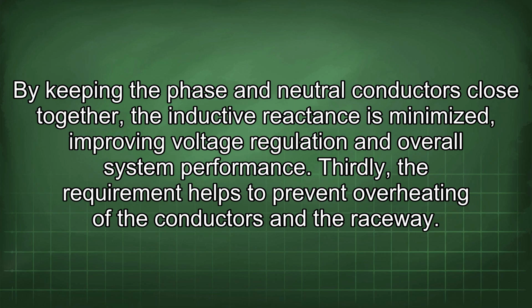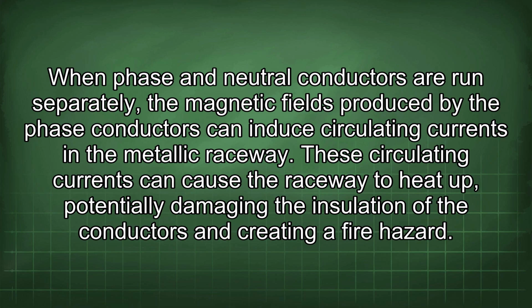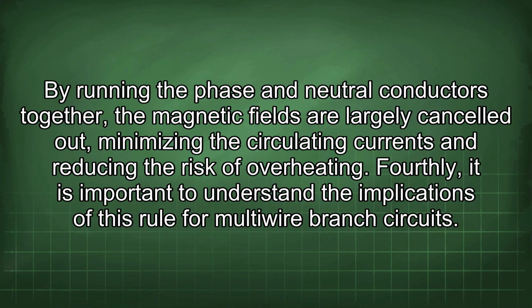performance. Thirdly, the requirement helps to prevent overheating of the conductors and the raceway. When phase and neutral conductors are run separately, the magnetic fields produced by the phase conductors can induce circulating currents in the metallic raceway. These circulating currents can cause the raceway to heat up, potentially damaging the insulation of the conductors and creating a fire hazard. By running the phase and neutral conductors together, the magnetic fields are largely cancelled out, minimizing the circulating currents and reducing the risk of overheating.